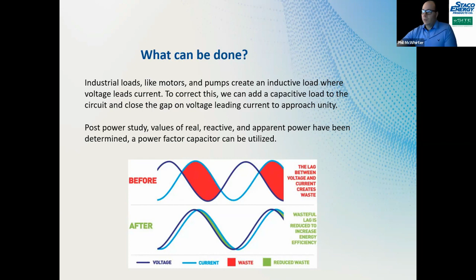Here's a little waveform I grabbed off of Google Images that does a very good job of explaining, like the waste with the foam and the beer, how power factor is interacting. You have this red in the middle, and that's like the foam. That's what's being wasteful, and some utility companies will charge you for that waste. You can correct that by adding some capacitance into your network, into your equipment circuits. Adding that capacitance will close that gap, reduce your overall waste, and increase your useful power, your real power, so that you can have better power flow into your equipment. All right, let's look at the next slide.